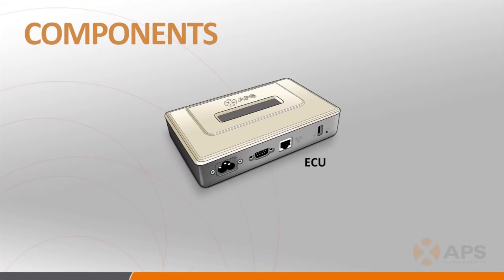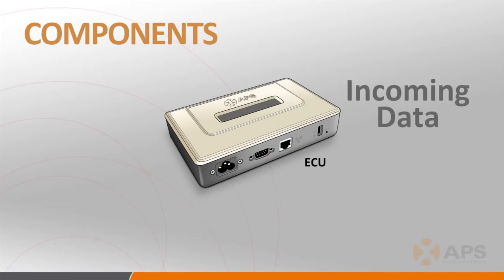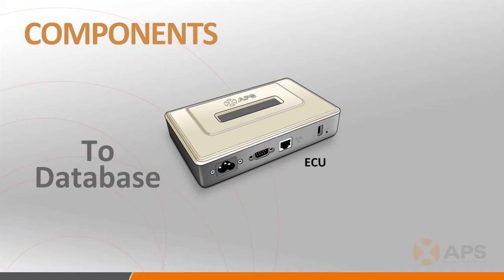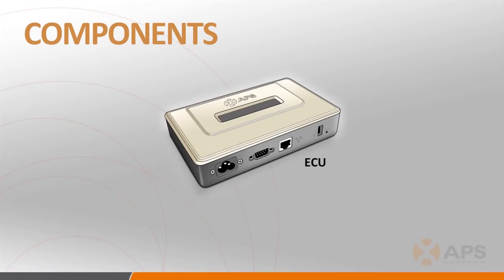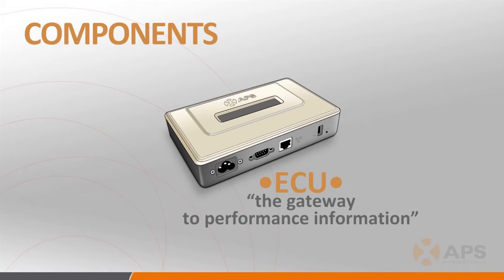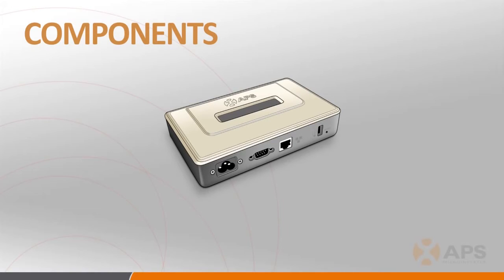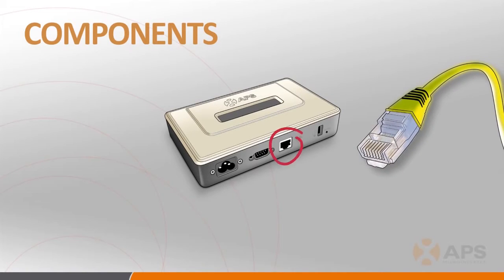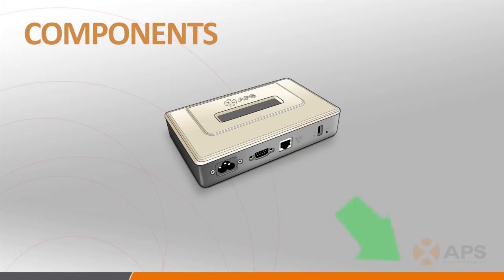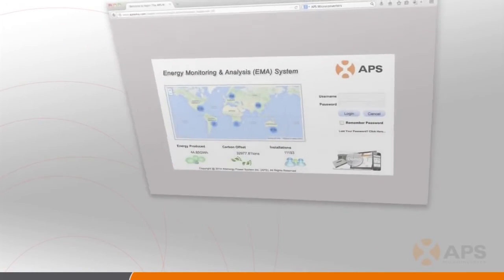The ECU collects and stores the performance data from each of the microinverters and sends it to the APS database so that the array can be monitored via the internet. The ECU, while optional, is an essential component of the remote monitoring system that should be thought of as the gateway to the performance information that can be retrieved from each inverter and its assigned PV modules. The ECU uses the PLC protocol to communicate with each of the inverters. Please note that the ECU is not a wireless device and requires an electronic bridge or direct CAT5 connection to communicate to a network router.